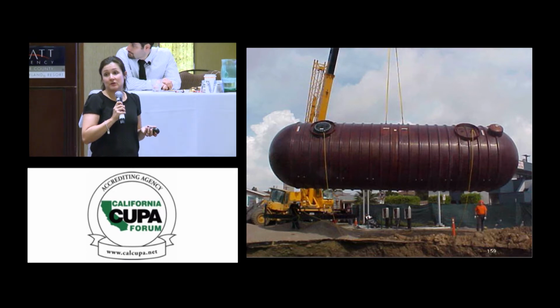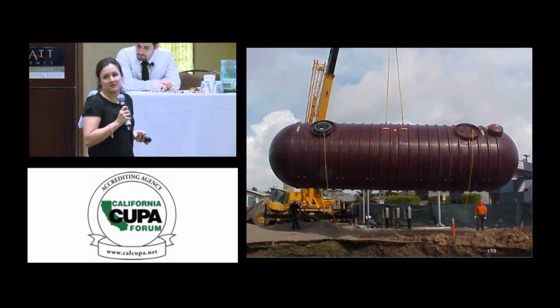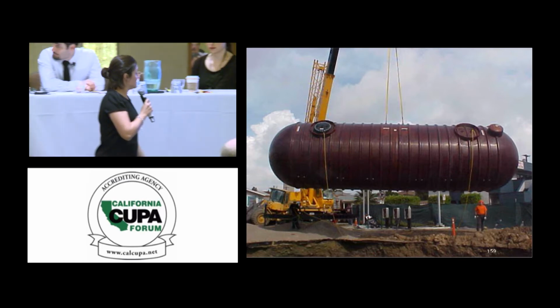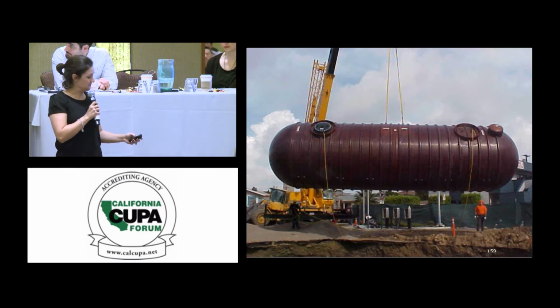It's not unheard of to have these bell sensors that are corroded. They've often opened up almost like a flower, and sometimes they even get stuck in there if they're not in good shape, because they don't fit through the opening anymore. So you're also checking for the cables. Make sure they're in good condition as well.